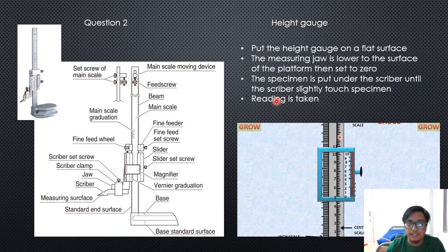For the next question, we need to demonstrate how to use the equipment shown in the question. The first equipment is the height gauge. This is the height gauge diagram, and this is the reading scale. How do we use it? First, we need to zero it. The scriber here needs to be on a level surface, and the reading here must be 0. If it is not 0, we must subtract it to obtain the correct measurement.